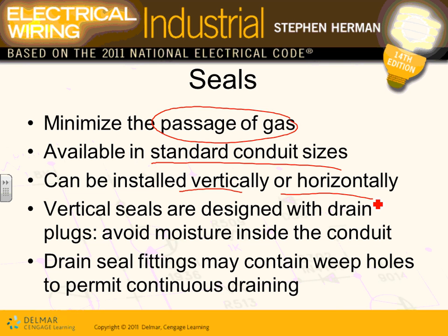Vertical seals are designed, if you are doing them vertical, they have something called drain plugs. If you seal here, what happens to the condensated water? It's going to turn into water and sit right here and basically damage your equipment. So what they do is they have little holes that allow the water, guys, from condensation to seep out. We don't want the water to sit. So they have something called drain plugs to avoid moisture inside the conduit.